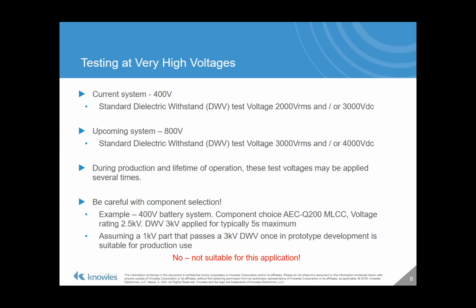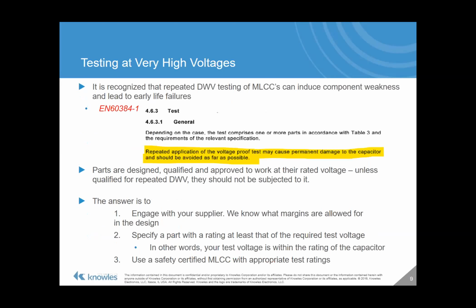If we just assume that we've got a 400 volt system and we can choose a 1000 volt part, we might test it. We might say it reaches 3000 volts, but we do that in our prototyping. No, it's not suitable for production use. You are overstressing that part every time it is tested, and that ultimately will reduce the reliability, result in lifetime problems. It's recognized that repeated DWV testing induces component weakness. There's a quote there taken from EN 60384-1. This is the main industry specification for capacitors, IEC EN specification. And it states very clearly, repeated application of the voltage proof test may cause permanent damage to the capacitor and should be avoided as far as possible.